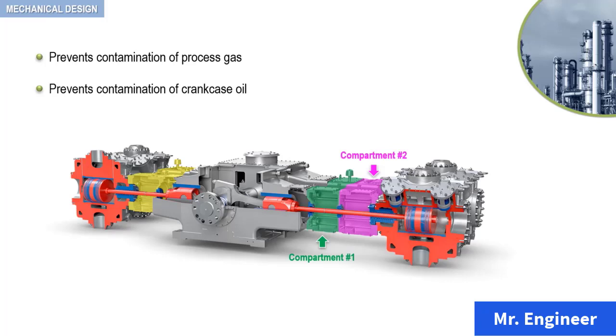Here, reliability considerations concerning this assembly are to make sure of the proper packing, partition packing, and wiper ring clearances. We will see this in detail further ahead using 3D animation and cross-sectional views.